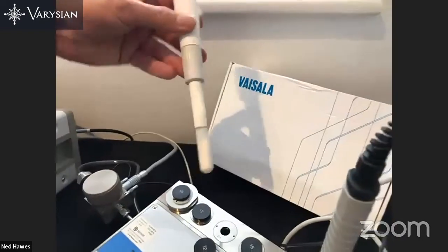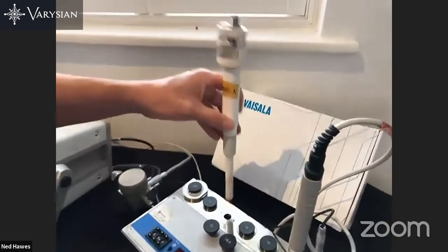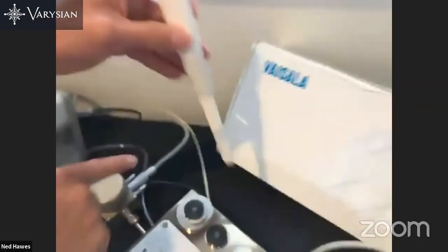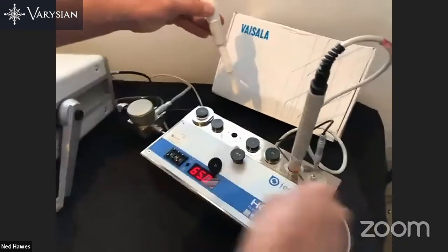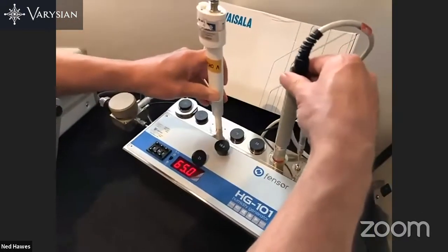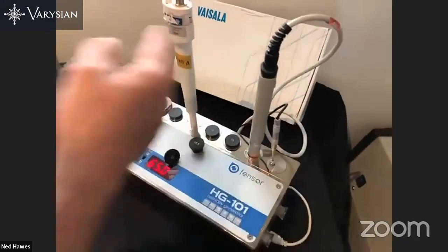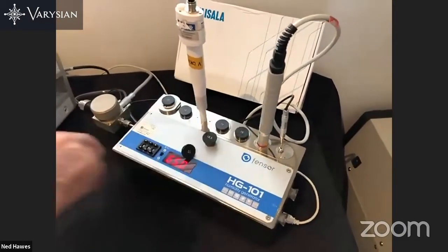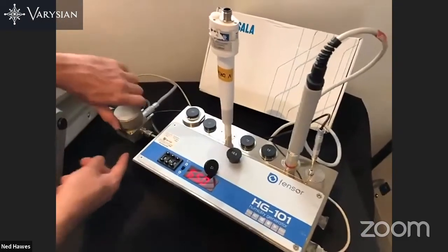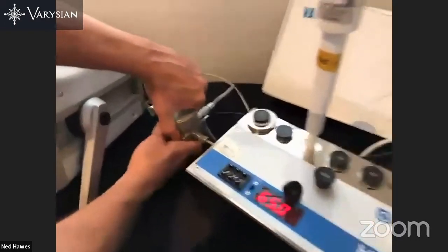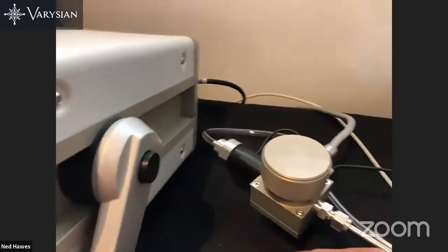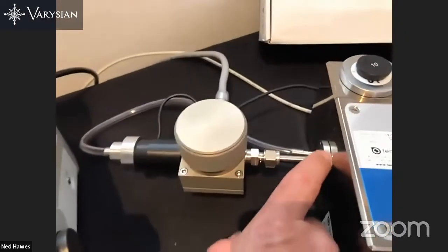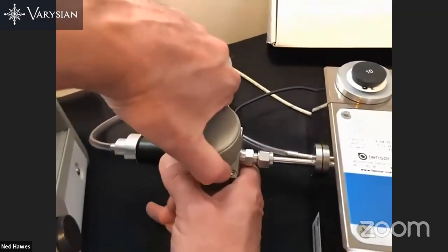This is a meteorological probe going into a chamber. There's a little box chamber inside, and the humid air flows back and around that way. So you've got two instruments under test here, both Vaisala. Just to show you the difference, this is the SH2, which samples out of the back side of the chamber.